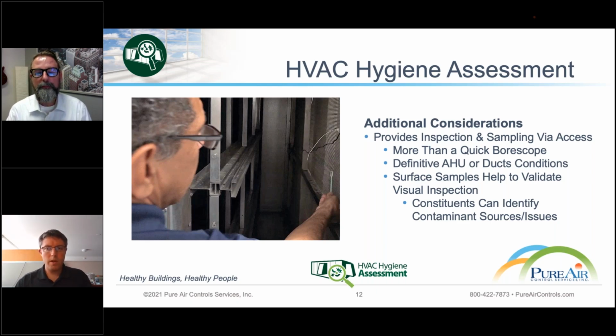So the overall goal is making sure we have a plan in place for you, identifying what's a problem, or helping you stay ahead of what's a problem. Some key foundational items here: it's not just coming in and looking at a cooling coil. It's looking at the drain pan, the filter rack, the blower, and getting into the ductwork as well. It's impressive how ductwork can play a role. You can have a dirty unit with fairly clean ductwork, or a clean unit with fairly dirty ductwork. It's always good to take a look at the system as a whole to make sure you're covering your bases.